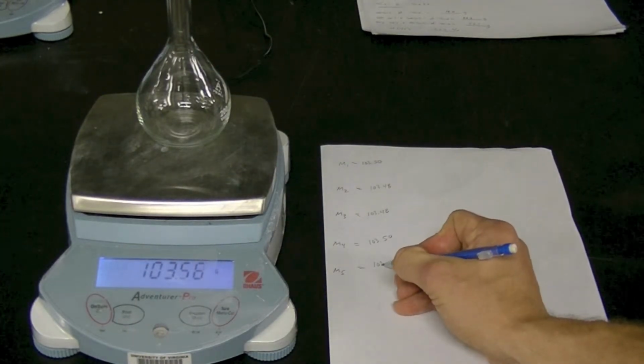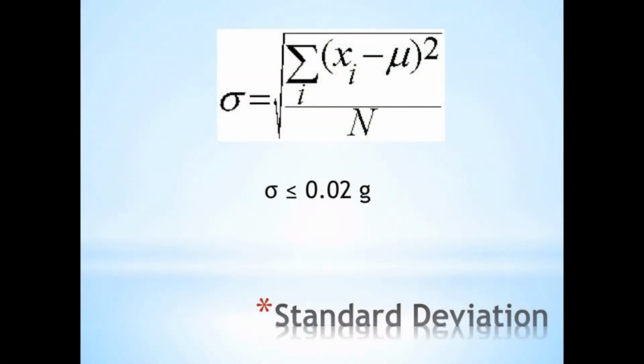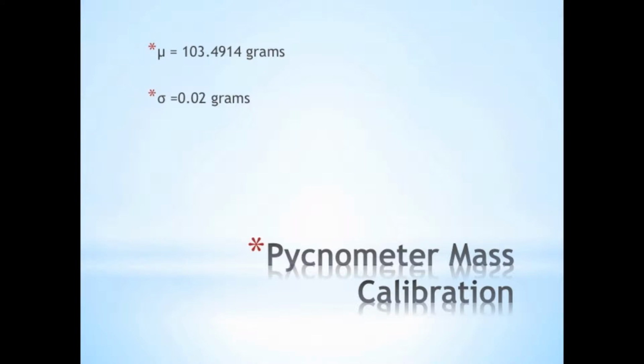With the 5 measurements, calculate the average, also known as the mean. Calculate the standard deviation of the dataset. The standard allows a standard deviation of 0.02 grams and below. If this requirement is not met, the calibration should be repeated. In our case, the average weight of the empty dry pycnometer was 103.4914 grams. The standard deviation of the 5 measurements came out to 0.02 grams. Thus, our pycnometer was appropriate for use.